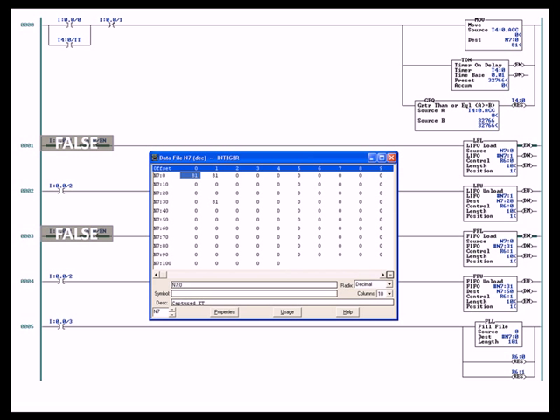It will also reset the position of the stacks. You see R6:0 reset, R6:1 reset, that will reset the stack position pointers so you can start from scratch. So if it gets all boogered up on you, just toggle switch 3, which is the fourth input. You have input 0, 1, 2, 3. The fourth input, toggle that on and off and that clears everything. You can start over.